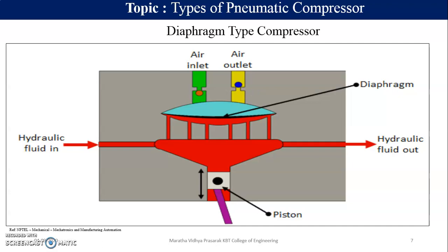These types of compressors are used whenever there is a small capacity requirement. Only then do we use the diaphragm type of compressor. Where contamination is undesirable, such as in food, chemical processes, industries and farming, I use the diaphragm type of compressor because no oil is allowed.